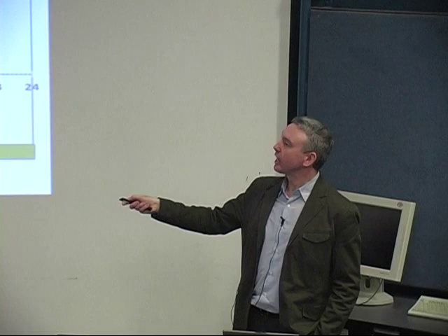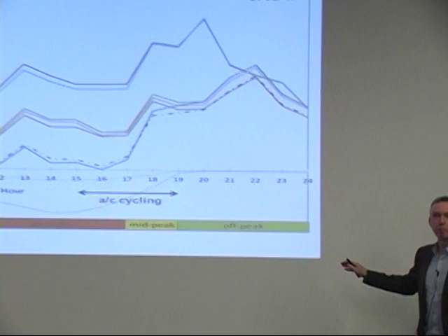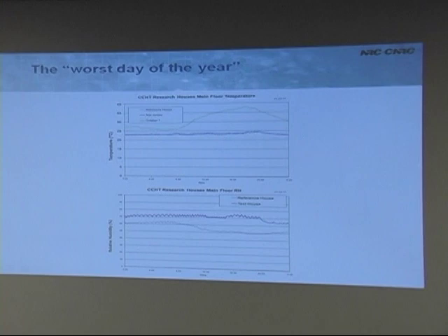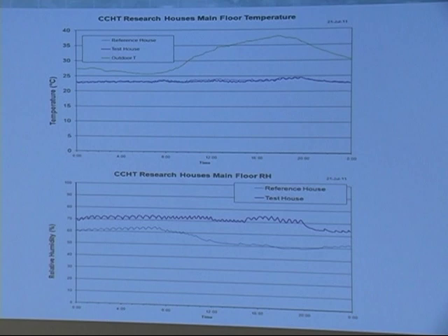With the photovoltaic power generation applied to the test house, we actually got demand down to zero during the on-peak period. A typical residential house, applying all these reasonable measures together, can get peak demand down to zero on the worst day of the year. The overall peak did shift later into the evening because of the washer and dryer load shift, but the utility is okay with that because commercial buildings have dropped off by then. On temperature, the better shading in the test house offset the reduced air conditioning, so there was no temperature impact. Humidity did rise from about 50% to 70%, which is slightly less comfortable but still within accepted comfort guidelines.